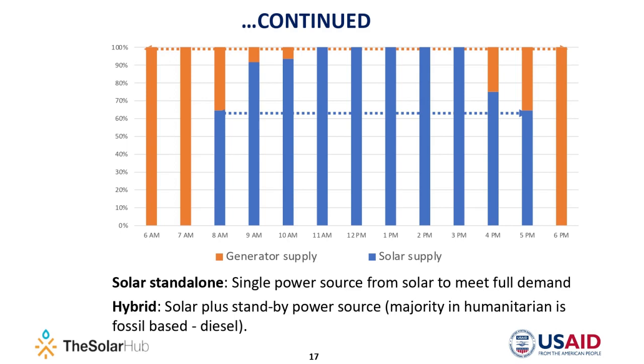And in many cases, we have seen in the field that when solar standalone is properly designed, taking into consideration the real conditions, it is able to meet the full demand. So it's all about rationalizing the design, and a second power source should only be introduced when it is clear that solar alone cannot meet the water needs together with other local considerations. We have come across many cases where the diesel generator is rarely switched on, but provides a peace of mind in case solar does not work, which is really anchored on false fear and doubts towards solar.